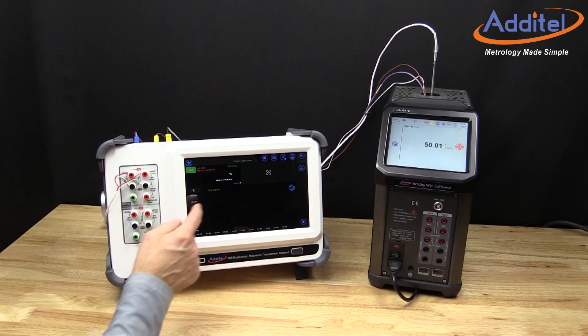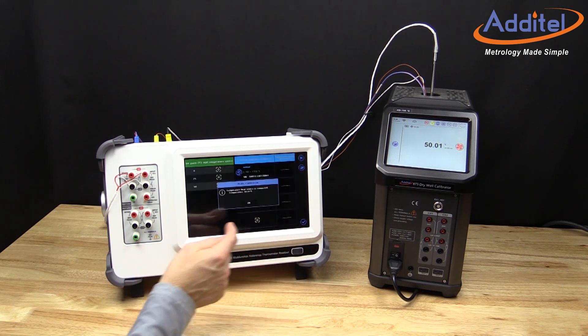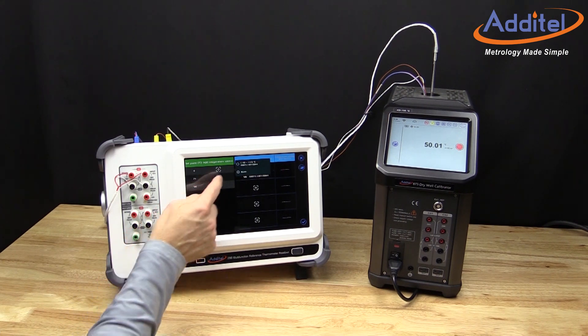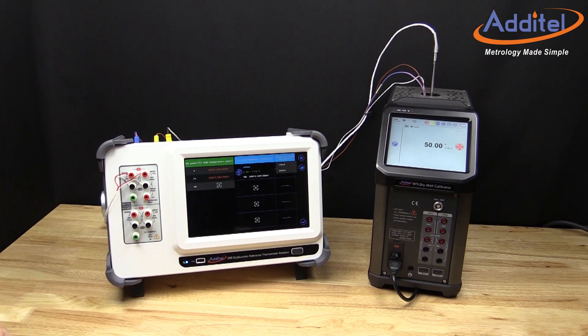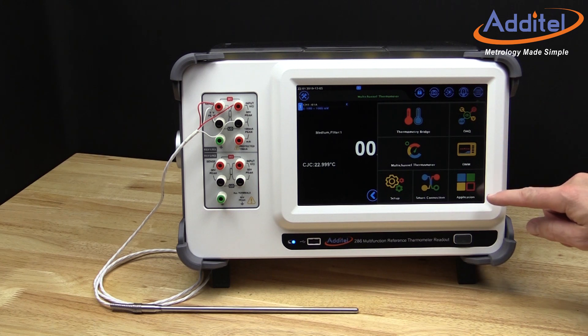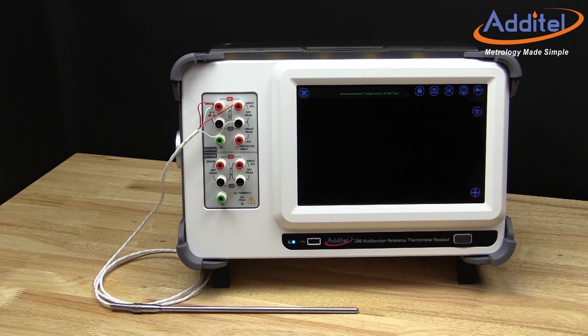The ADT286 readout is capable of controlling both Additel and other manufacturers' heat sources to facilitate truly automated temperature calibration processes. The ADT286 is capable of collecting data and generating reports with no software required, providing a turnkey temperature calibration solution. In addition, wireless communications with Additel's heat sources is a standard feature.